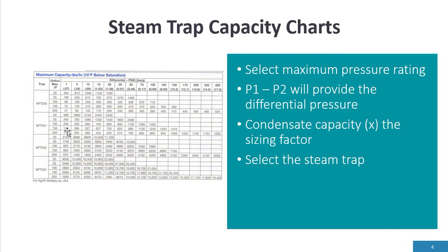We have to come down to the next model steam trap with 150 psi, and the capacity is now 990 pounds per hour. Therefore, we come up with the correct steam trap selection.